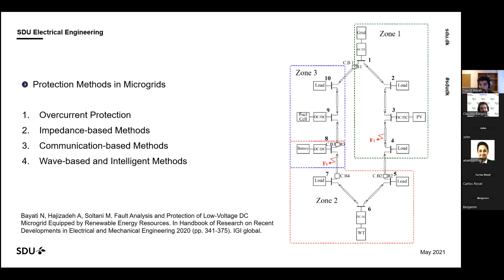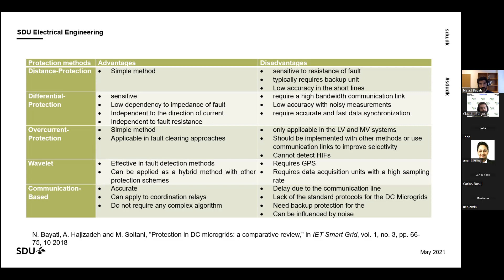The protection of power systems has relied on overcurrent protection, impedance-based protection, for example distance relays, communication-based protection, and some new methods, for example wavelet-based and intelligent methods. So we can also modify them to implement in some larger power systems. If we focus on the different methods that can be applied to microgrids, or especially DC systems, we have different advantages and disadvantages for them, and you can see that here. We don't have any perfect methods, so we need to more or less modify a method or make new methods for these systems. So traditional protection systems and traditional relays cannot be applied to DC microgrids.